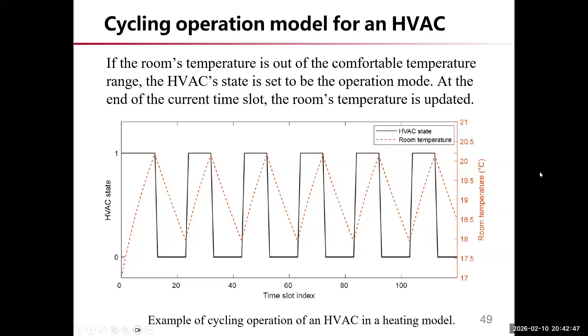Here, the minimum time slot is 1 minute. So you may set it open for like 15 minutes and close for like 10 minutes and open for like 8 minutes again and again. That's the cycling operation mode with the simple rule. It can be more complex if we set multiple time slots with different set rules and set temperatures. For example, we can divide it into multiple time slot sets, where different temperatures are applied with U set 1 and U set 2, respectively. Which means that the comfort band for different time slots is different.